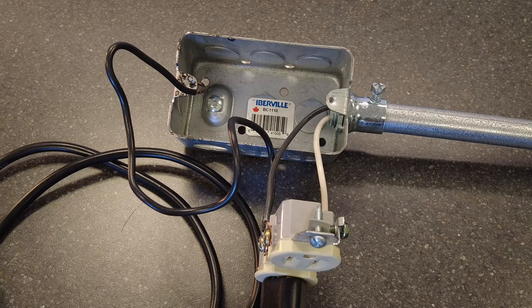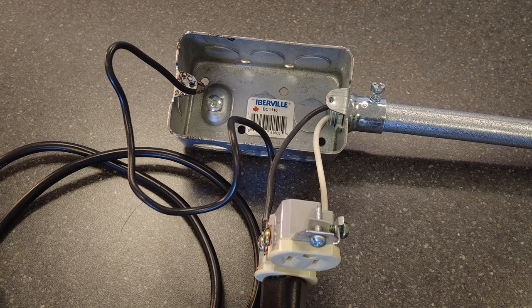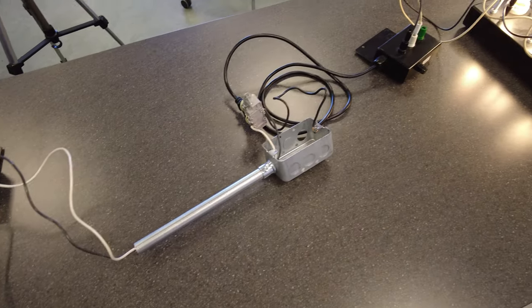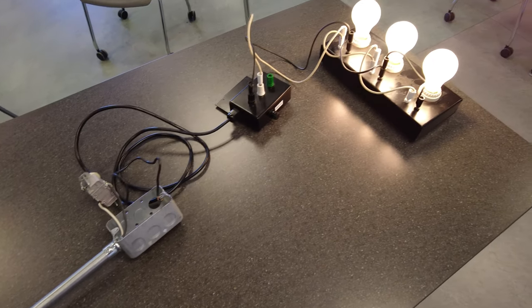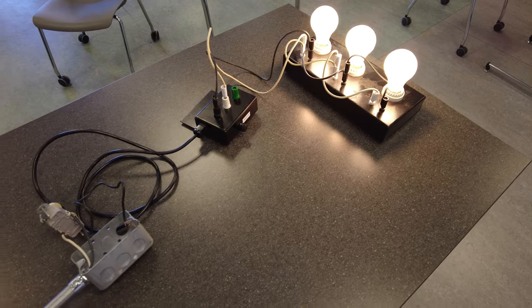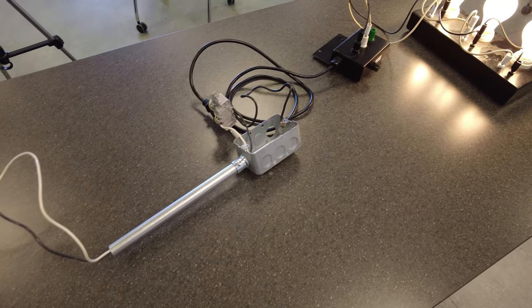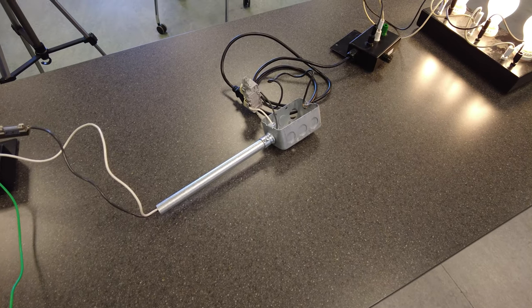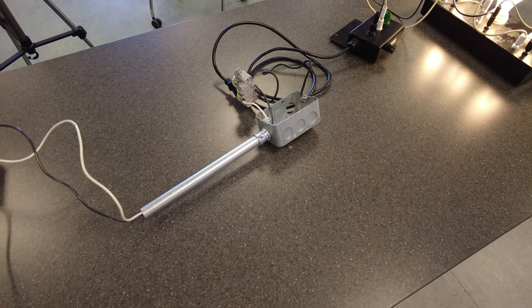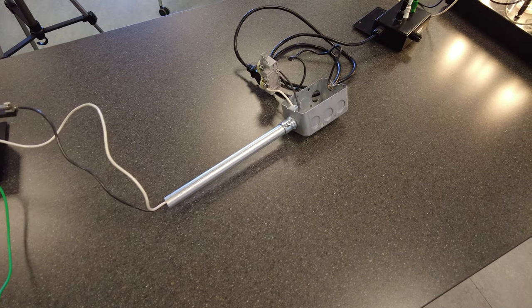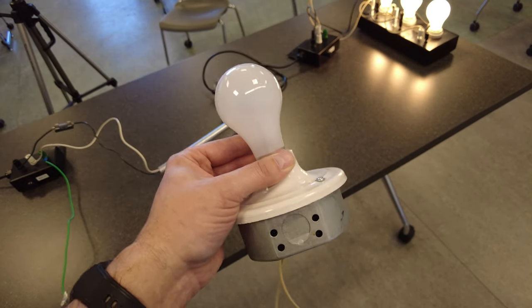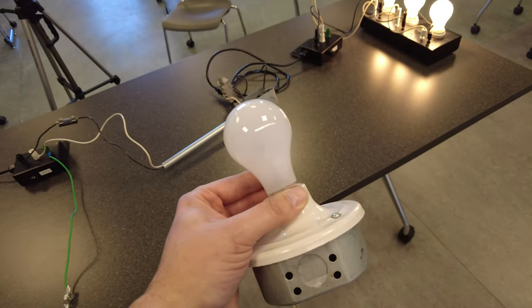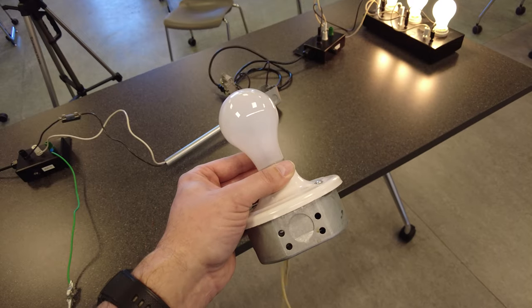As you can see, that hot conductor with the hook on it is now in direct contact with that 1110 electrical box. In this situation, there's a very real but invisible threat. And that's why I created this demo - just to highlight this very real and invisible threat. So right now, the fact that this circuit is not tripped, there is a potential on that box and that EMT of 120 volts. So what I have here is just a standard incandescent light bulb with two leads coming off of it.